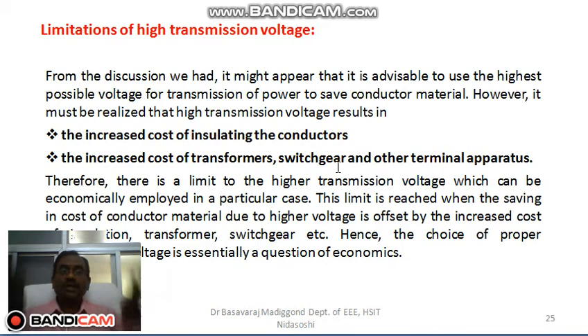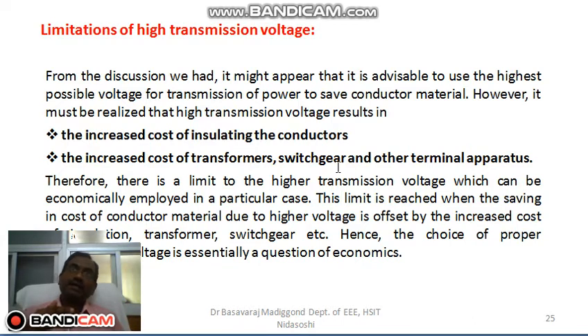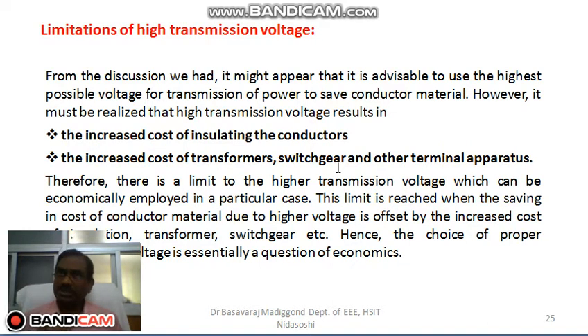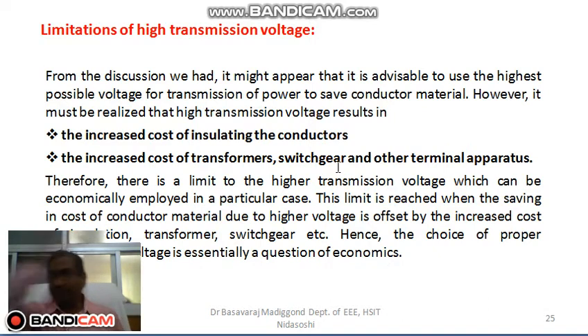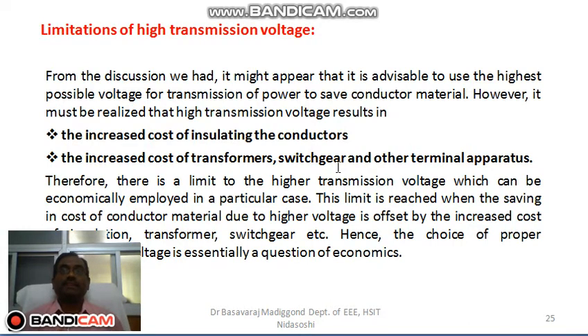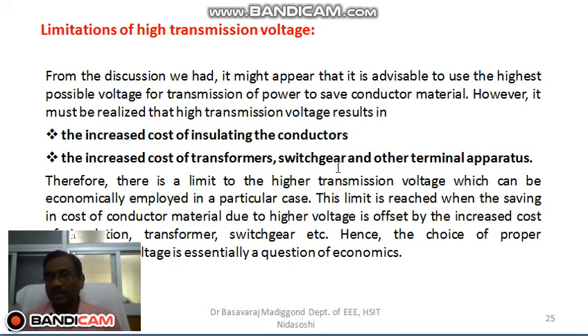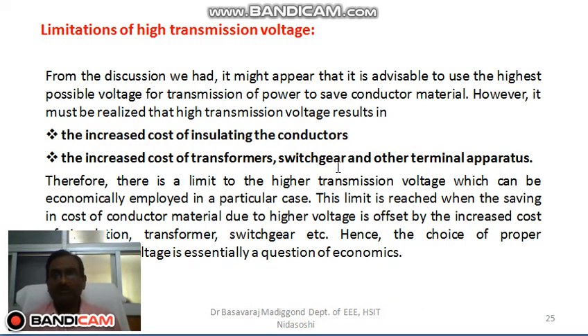As the transmission line voltage increases, the number of insulators required will also increase, raising the cost of transmission. Furthermore, the supports required for laying the transmission line — which carry the insulators — need to be heavy supports, which again increases cost. If the transmission line length is more than 500 kilometers, there will also be stability issues.